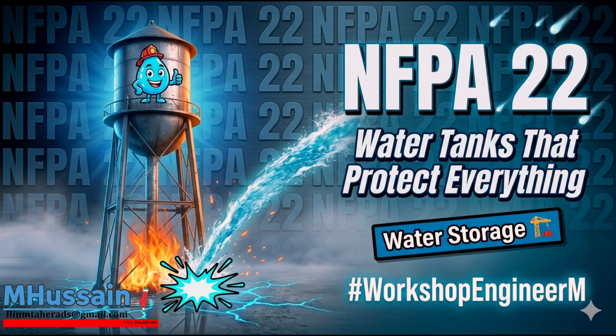Let's run the math on that to see the scale. Yeah. If you specify a 300,000-gallon private water tank, filling that in 8 hours requires a constant flow rate of 625 gallons per minute. Which is massive. Right. That isn't just a domestic water line. That requires a dedicated, heavily engineered municipal tap, specialized backflow preventers, and a massive control valve array just for the refill mechanism. And you have to guarantee the city can even provide that 625 GPM continuously for 8 hours without dropping pressure to the surrounding neighborhood. Exactly. The refill mechanism requires as much hydraulic engineering as the discharge system.